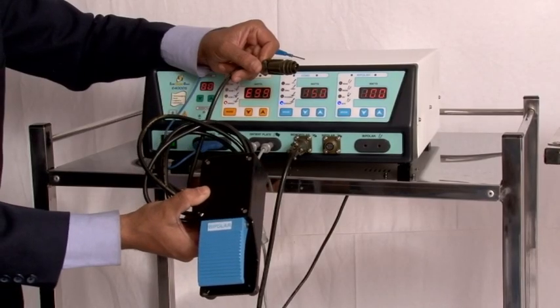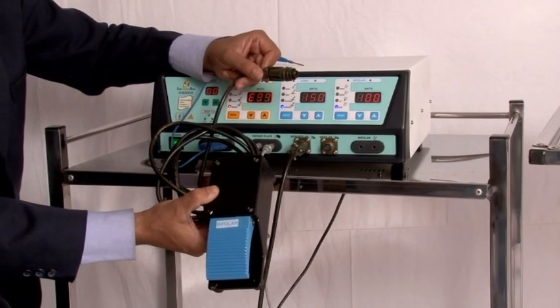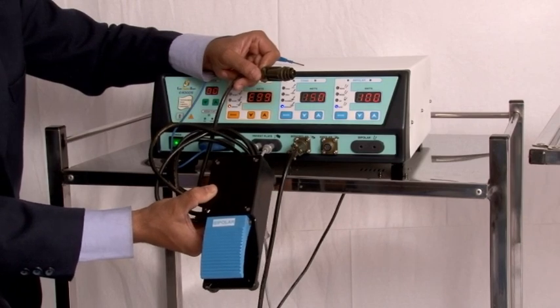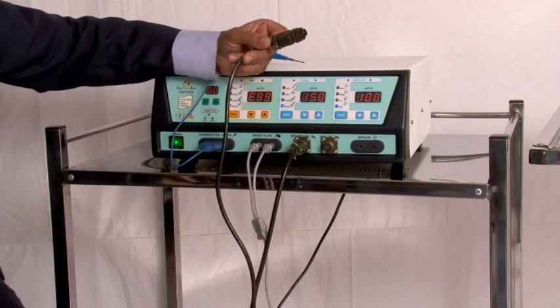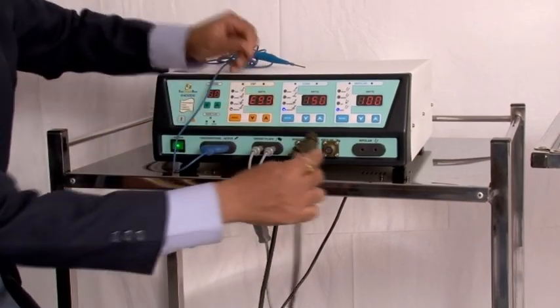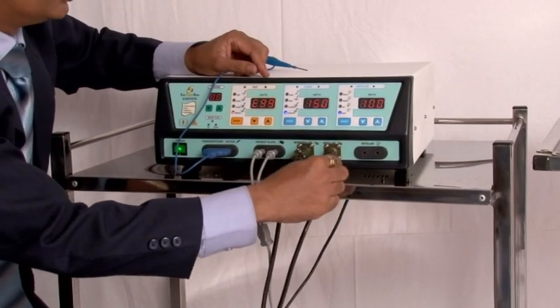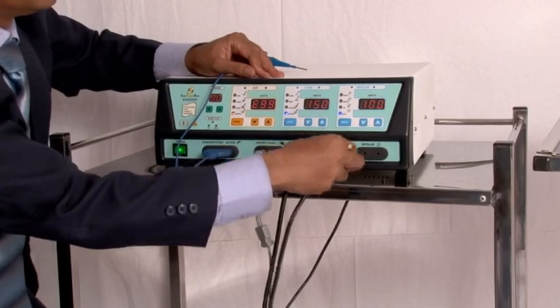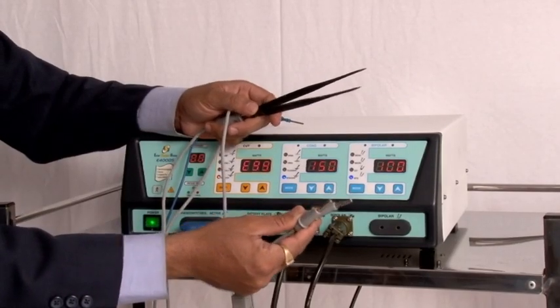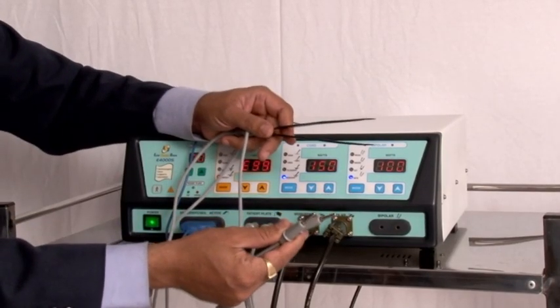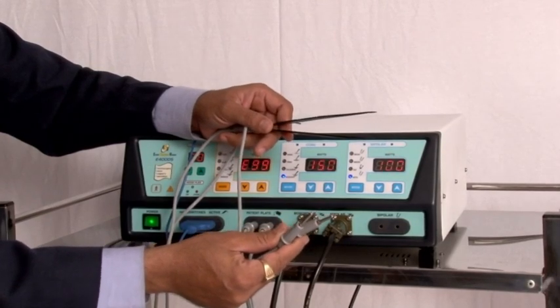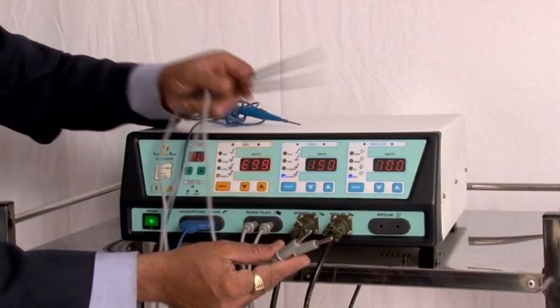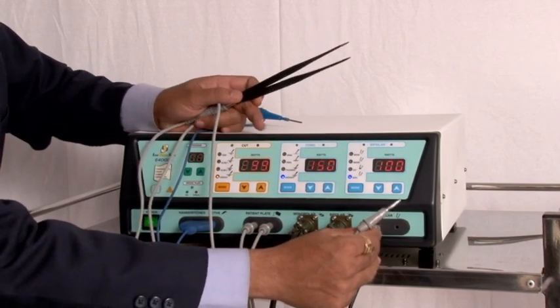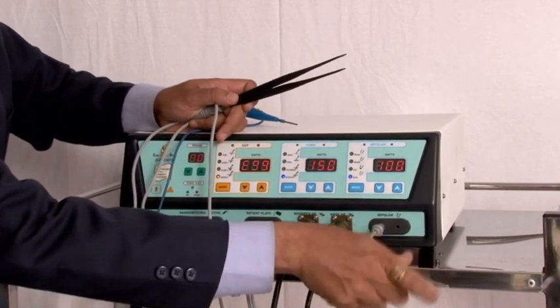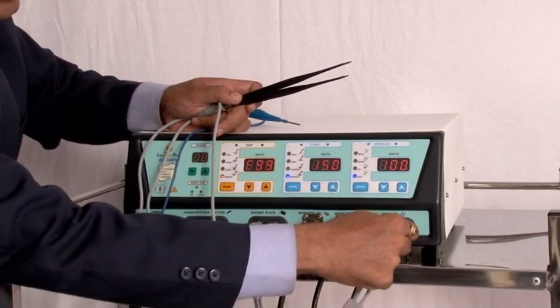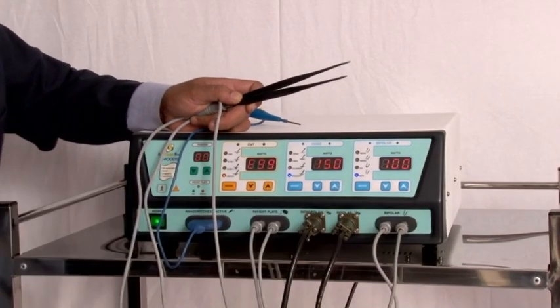Fifth accessory is bipolar foot switch. Blue paddle of this foot switch is for bipolar outputs. Bipolar foot switch is attached to the machine at jack bipolar foot switch. Sixth accessory is reusable bipolar forceps. Bipolar forceps along with its wire is autoclavable and is operated by foot switch. It is attached to the machine at output jack bipolar forceps.